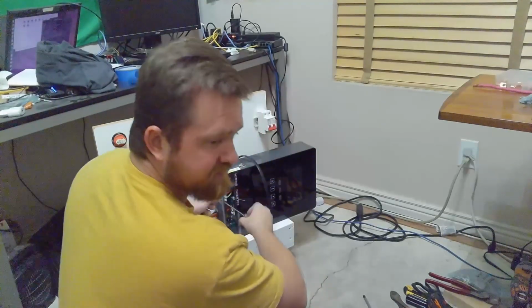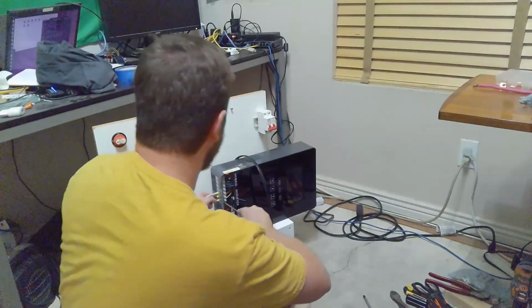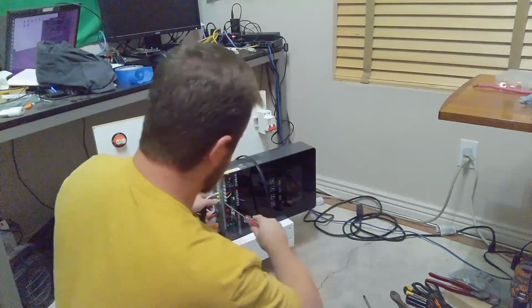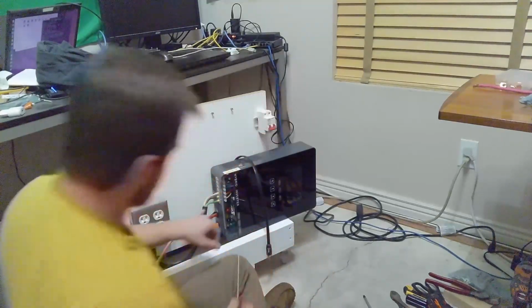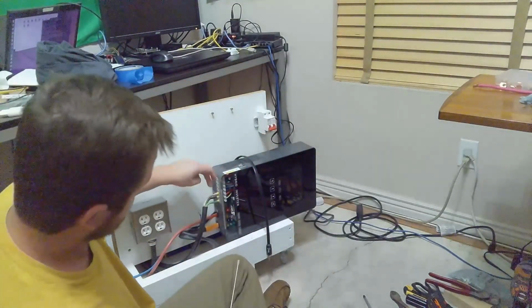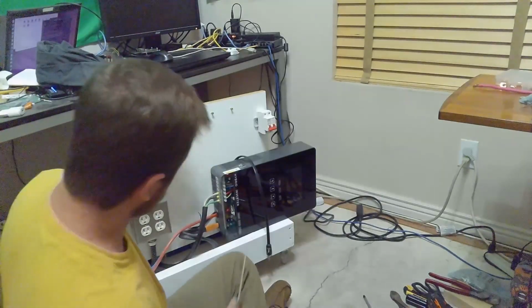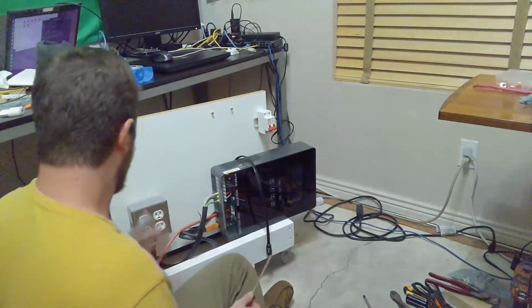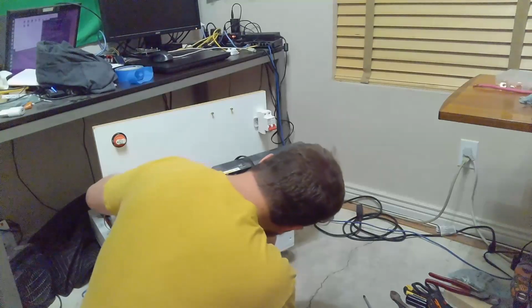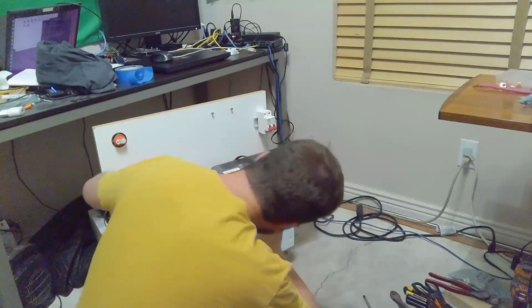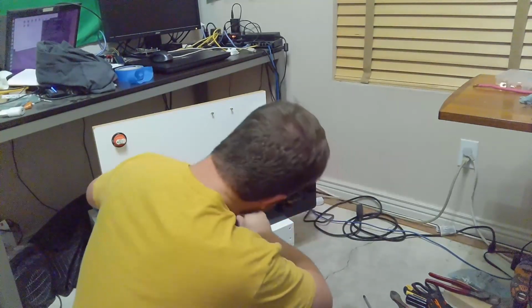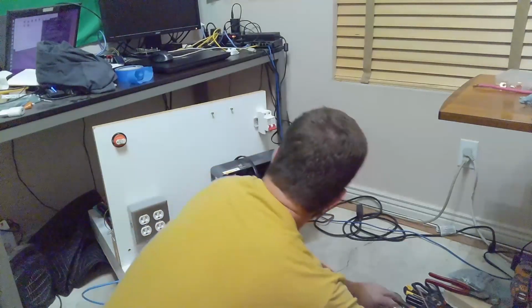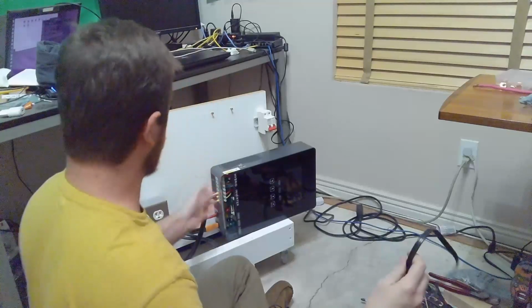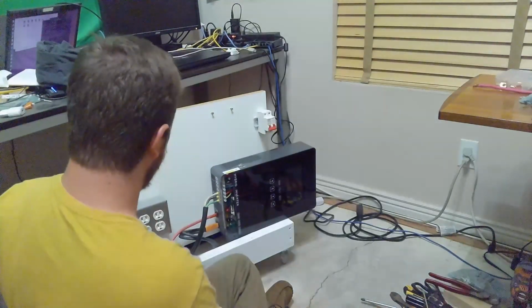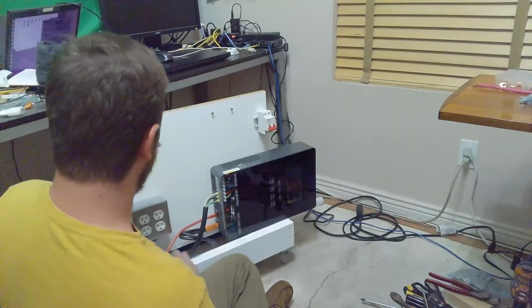I've disconnected the grid side just because the grounding terminal will need to run out of the panel, but line and neutral are hooked up, and the battery's hooked up. I'll hook up the COM port here, then mount it and hang it, and we'll do a power-on test to see if it works. Then I'll redo this—probably add a switch right here so I can turn it on and off to charge off the grid if I need to.